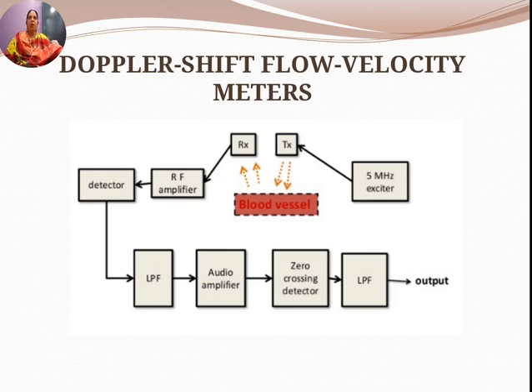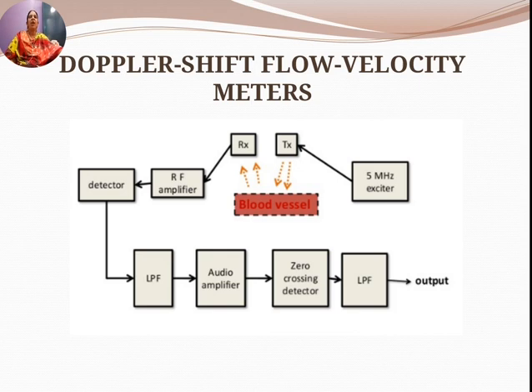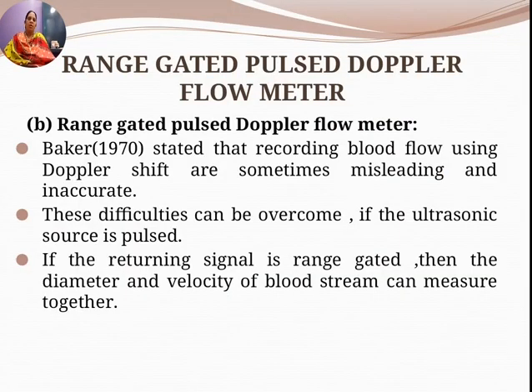In the block diagram of the Doppler shift flow velocity meter, ultrasonic sounds from the transmitter (TX) pass through the blood vessel and are received by the receiver (RX). The signal is amplified and detected, goes to a filtering circuit, and is further amplified using an audio amplifier before presenting the output through a low pass filter.